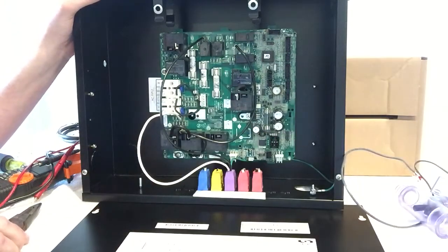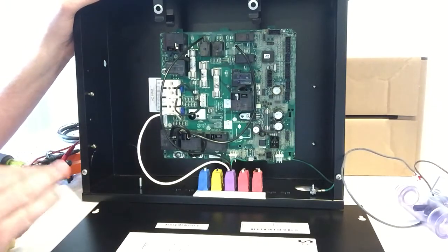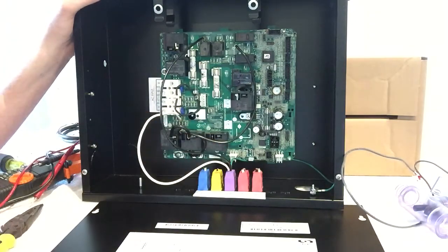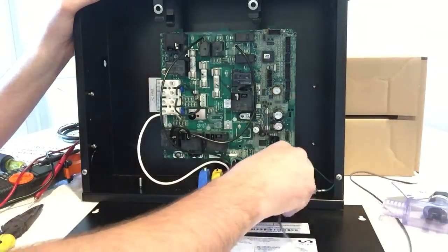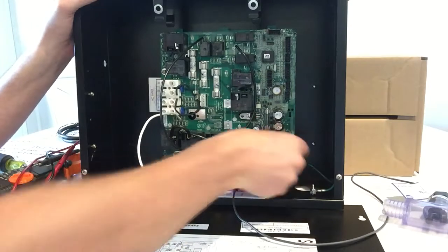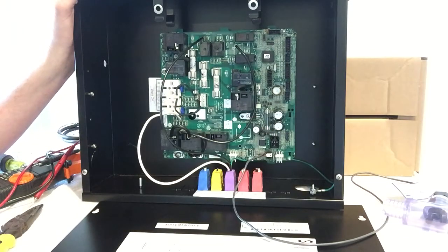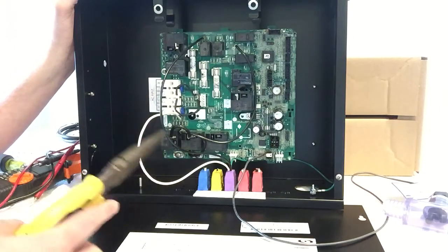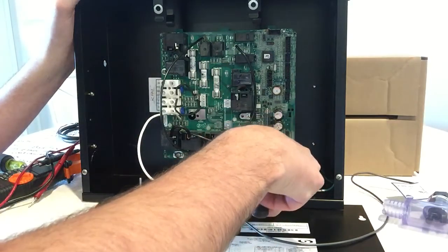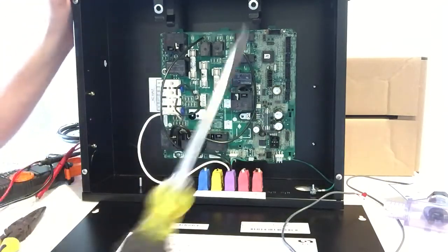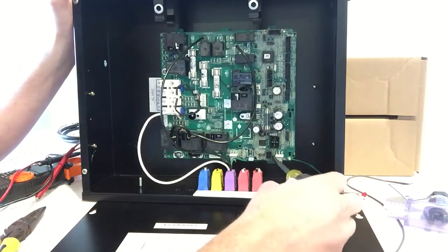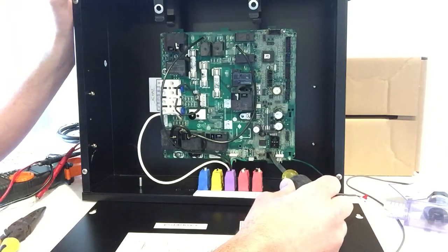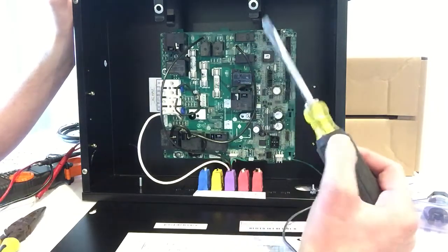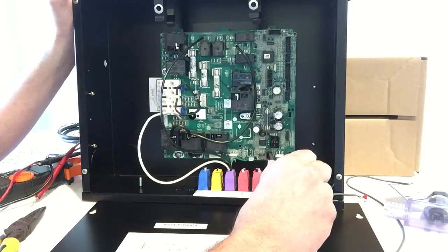If your pump was cycling and now the pump's running consistently, your flow switch is bad, because your flow switch is causing it to cycle like that. However, if your circulation pump is running consistently, no problems, you are still going to unplug your flow switch carefully from P10, and you could do one of two things. You can take a flathead screwdriver and literally bridge the two pins on the PC board with it. You don't need to push hard, you just want the two pins to touch the flathead at the same time.